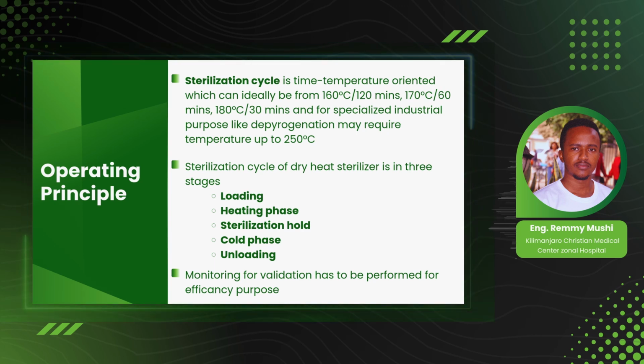Okay, the sterilization cycle of this dry heat sterilizer is made up of three stages, which are already bolded here, but we have included two additional stages just for those who are not aware of how to use it at all. There is a loading part, in which you insert the materials or the things that you need to sterilize, and there is a heating phase. The heating phase is where the heating element inside raises the temperature from room temperature up to the desired temperature that you have already set. If it is 170 degrees, it means it will rise from room temperature to 170 degrees. That is the heating phase.